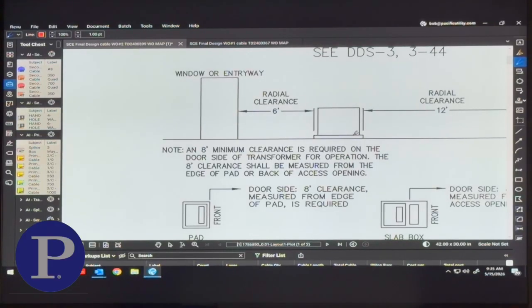When you're on the transformer side and you're pulling cable up to the transformer, you want to pull about 4 feet off of the top of the pad. So if this is your transformer in here and your secondary ducts, or you're going to have a handhole sitting in here, your secondary ducts are going to be located on this side of the transformer. If this is the front, you want to pull this up, and from this point right here, you want to pull 4 feet, roughly about 48 inches.